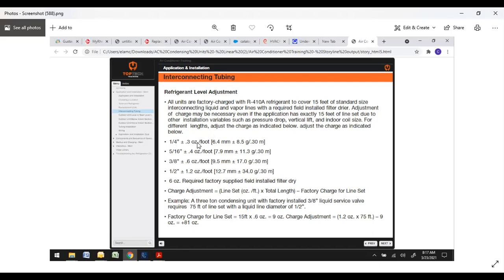So these are going to be your gross charges. If you know your specifics on your line set, so if you have a 20-foot line set and you know what your fittings are, you can add those up and then you can initially add additional line set. So if you have a 3/8 line and you have an extra 5 feet, you would take 0.6 ounces times 5, and that would be your additional gross weight charge. Don't take that as being the end-all charge. That just gets you close, so you know you're within the ballpark. But that's not going to be your final charge. We'll get into that later.